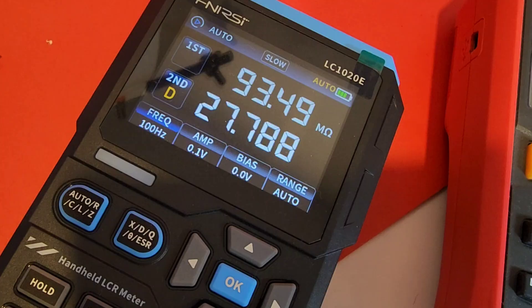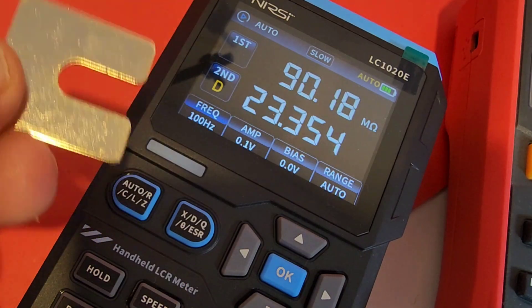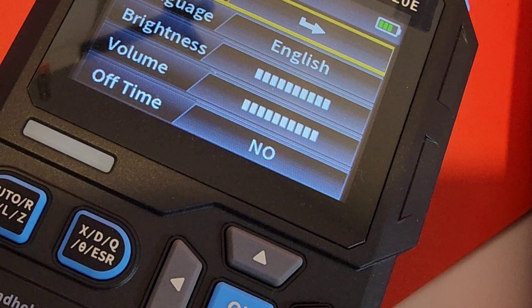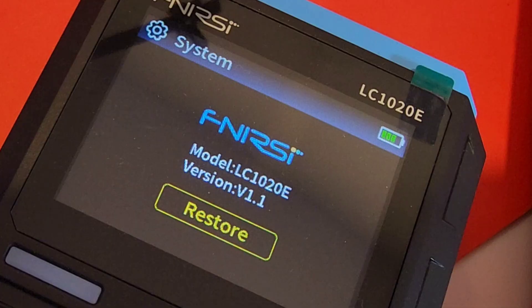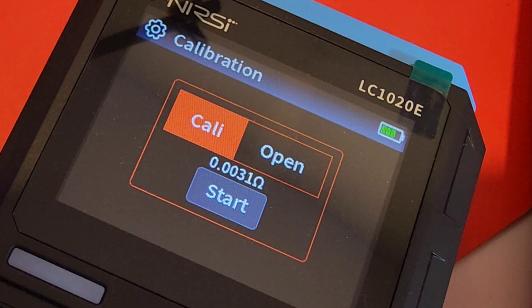You just got your brand new FNIRSI LC-1020E LCR meter — first thing you've got to do is calibrate it. Calibration involves your little shorting tool. Insert that short tool in like so — now we are ready for calibration. Hold down on the OK button to bring us into the main menu. Once we're in the main menu, scroll down to calibration. There's also a system setting that tells us the model and version number 1.1. You can also download firmware for your FNIRSI. Now back into calibration — hit the OK button. We have our shorting tool in the high and low, and we're going to start a calibration. Before entering the calibration function, make sure you have already shorted the two plates using the shorting piece the meter ships with.